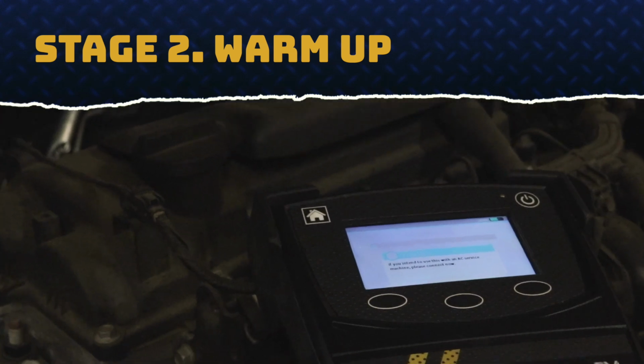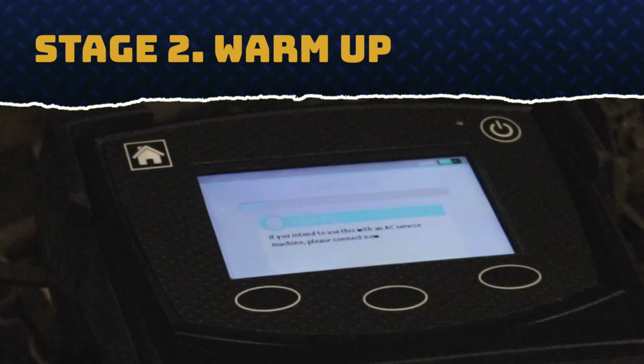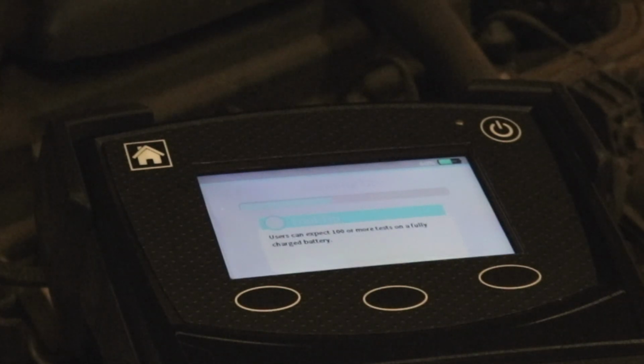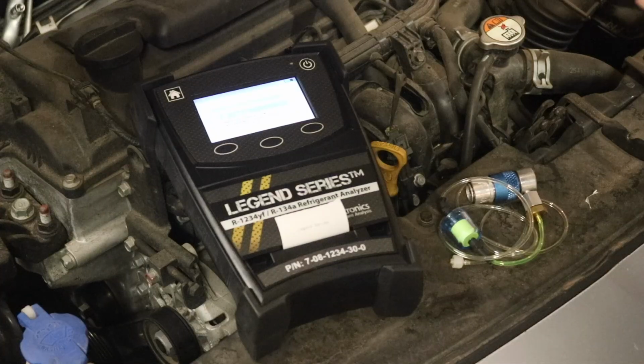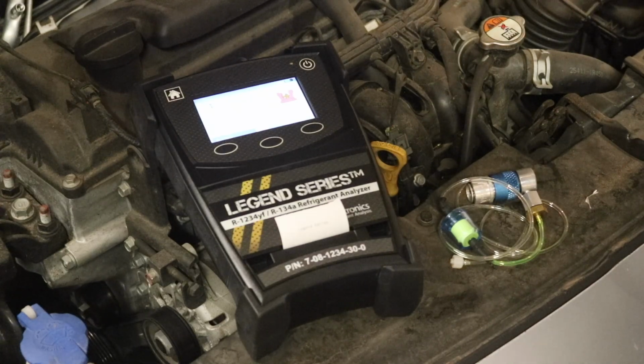This is the warm-up stage, and typical of software, we get a progress bar that shows that the tool is going through a warm-up where it's bringing the sensors up to the temperature that it needs. Again, this takes generally less than 30 seconds. Okay, just about at the end of the warm-up stage now. In this second phase, we're given the option to choose the refrigerant we think we are looking for.